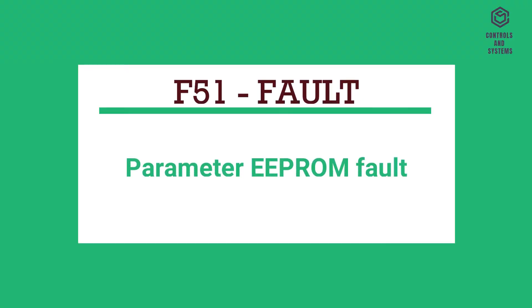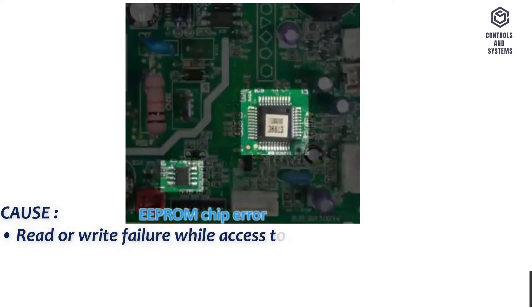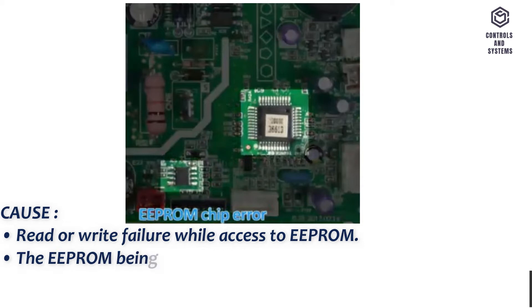F51 Fault: Parameter EPROM Fault. Cause: Read or write failure while accessing EPROM. The EPROM being full — too many parameters have been changed.